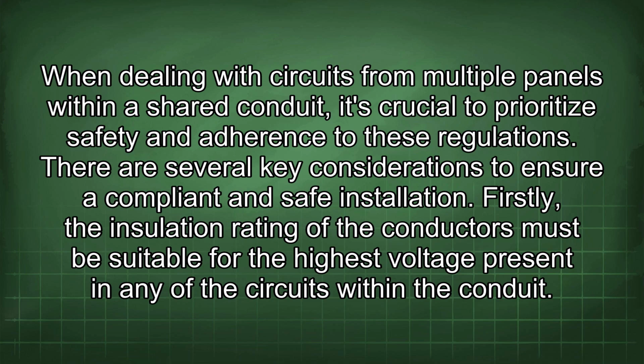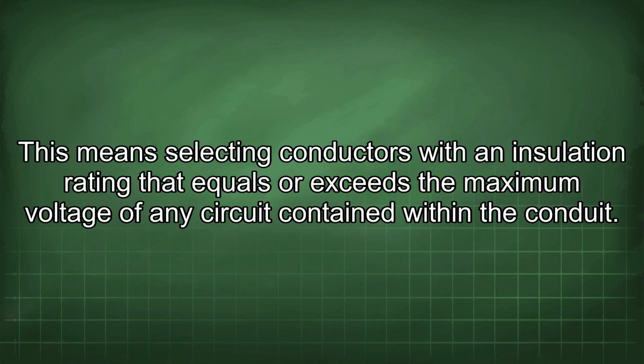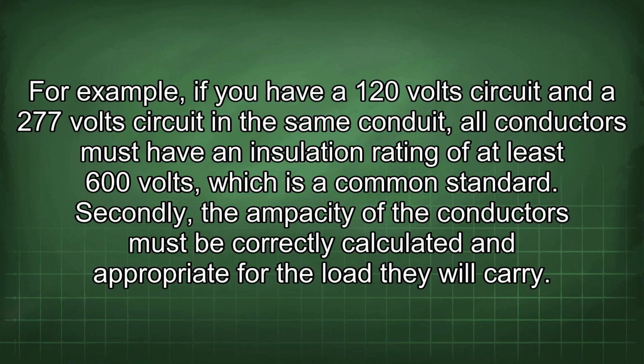Firstly, the insulation rating of the conductors must be suitable for the highest voltage present in any of the circuits within the conduit. This means selecting conductors with an insulation rating that equals or exceeds the maximum voltage of any circuit contained within the conduit. For example, if you have a 120-volt circuit and a 277-volt circuit in the same conduit, all conductors must have an insulation rating of at least 600 volts, which is a common standard.